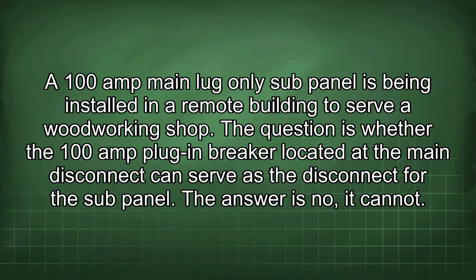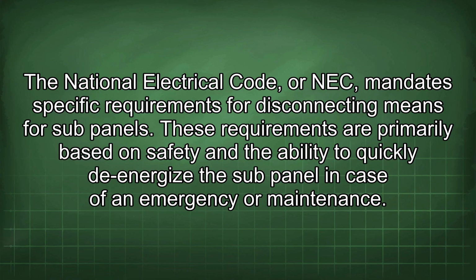A 100 amp main lug only sub-panel is being installed in a remote building to serve a woodworking shop. The question is whether the 100 amp plug-in breaker located at the main disconnect can serve as the disconnect for the sub-panel. The answer is no, it cannot. The National Electrical Code, or NEC, mandates specific requirements for disconnecting means for sub-panels.